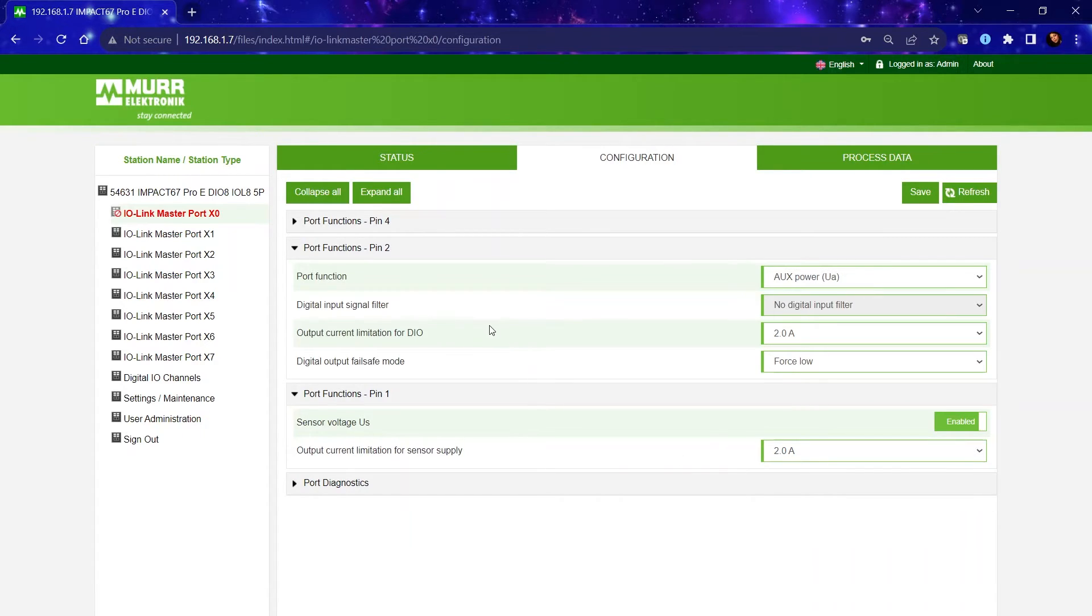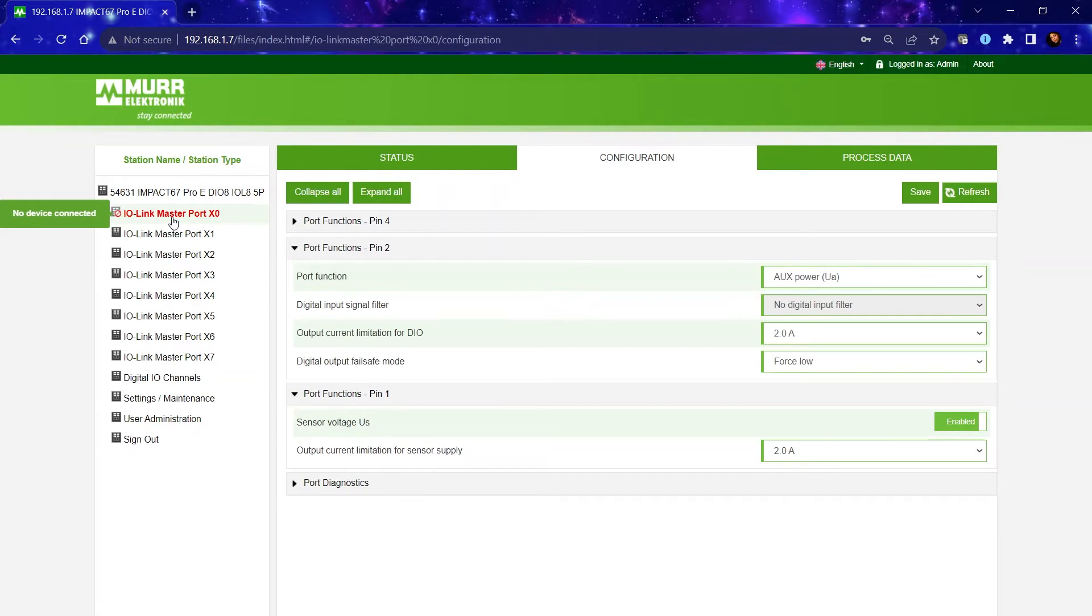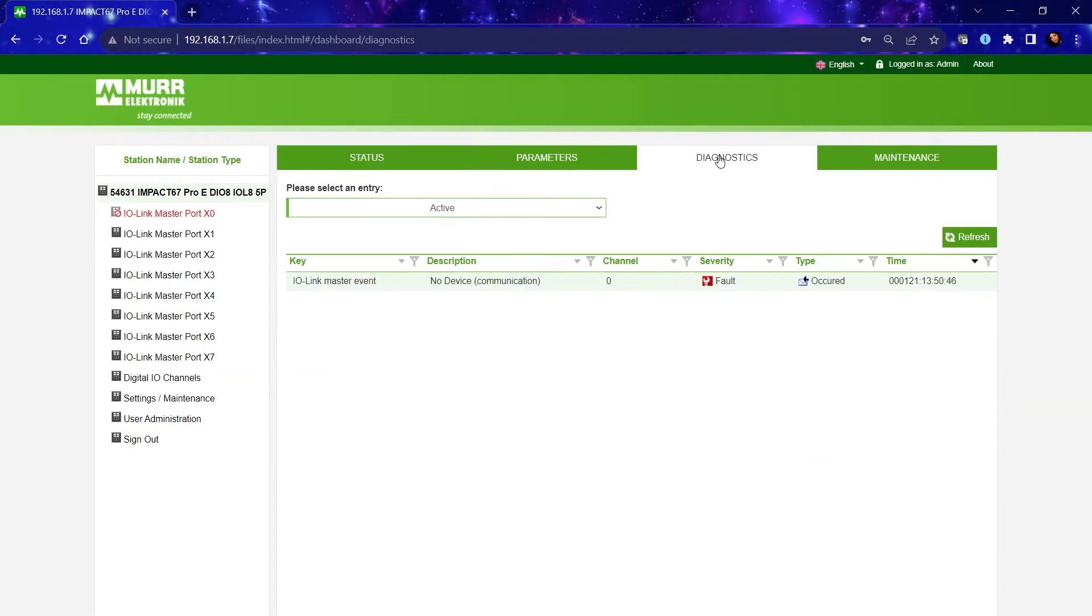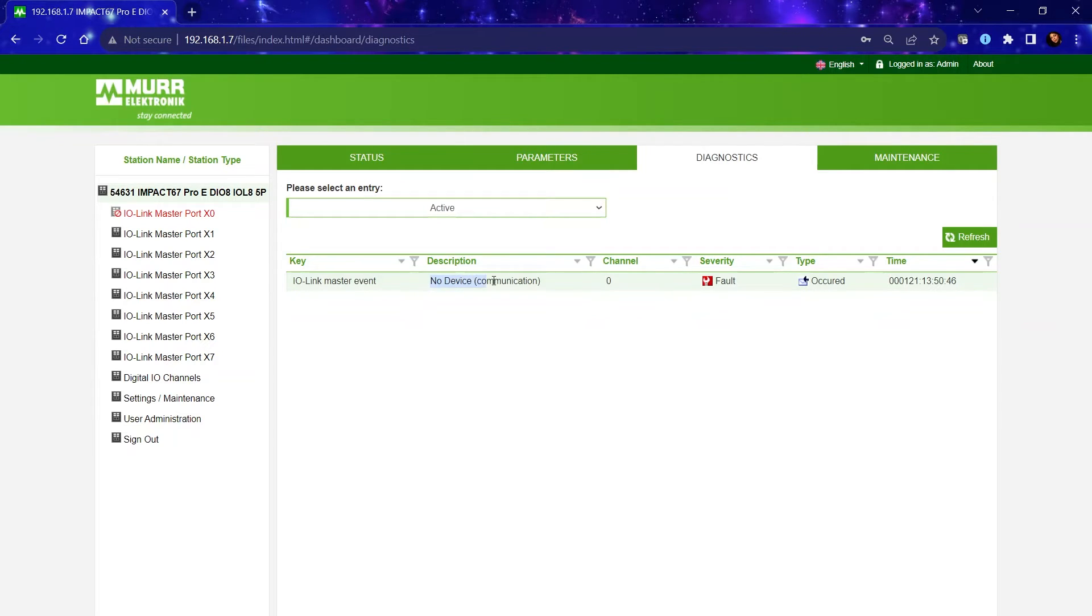Now I'm sure you're pretty curious, why is there red text on the left-hand side? This is telling you that there is a diagnostic that is occurring right here on this port. To know exactly what is the issue, I have configured that port as IO-Link but I do not have a device connected to it, specifically an IO-Link device.